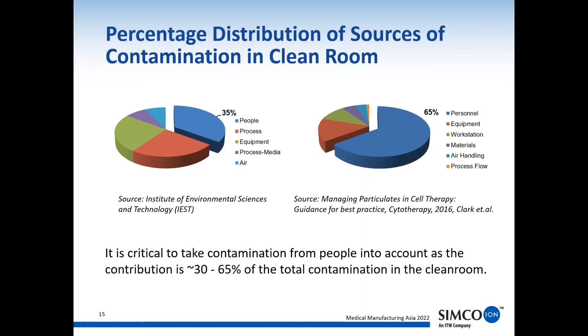If we can reduce that in some way, that's going to make everything better. What we found is that if we are careful and we ionize the change room and the garmenting process, and don't ignore the people as they're coming into the clean room, and don't ignore the airlocks where product is being brought in, and actually ionize those environments, we can reduce the amount of contamination brought into the clean room to those very dirty locations.